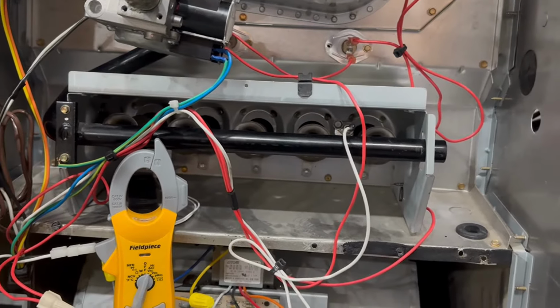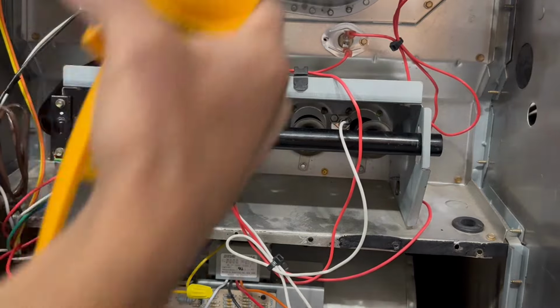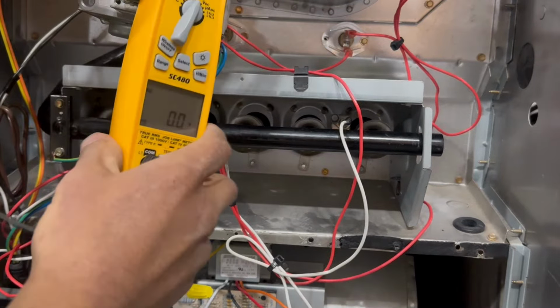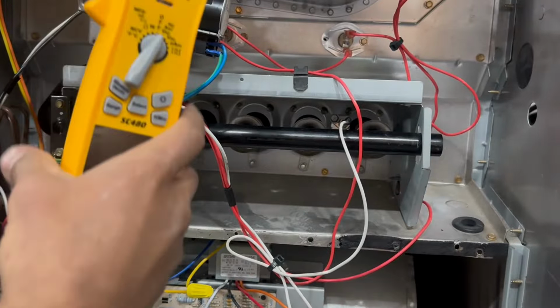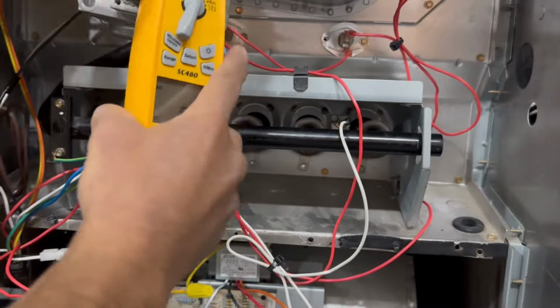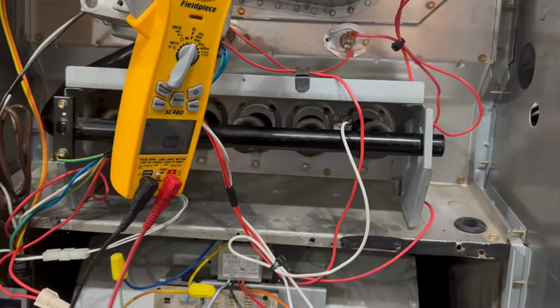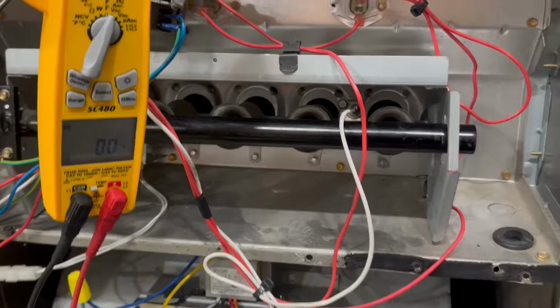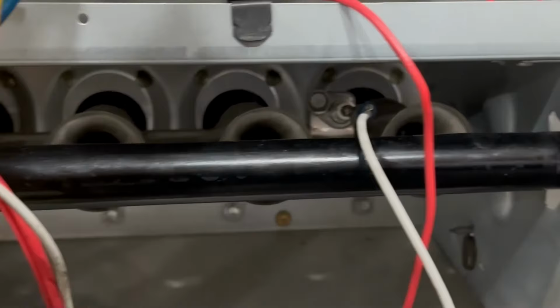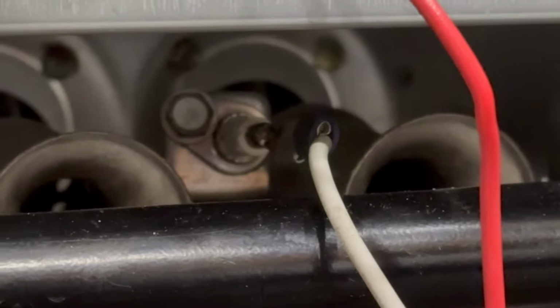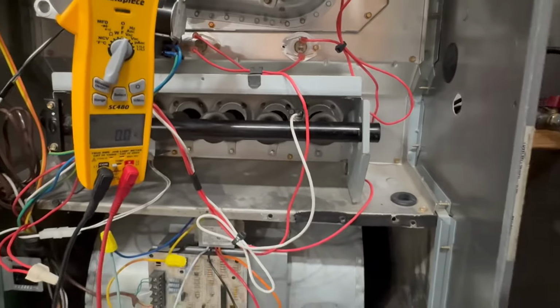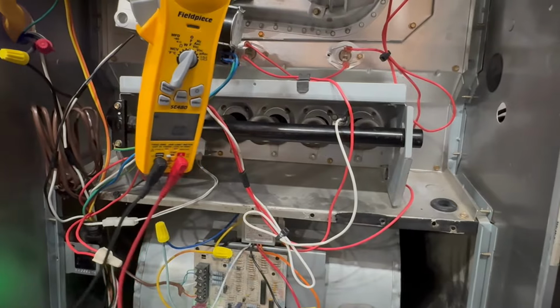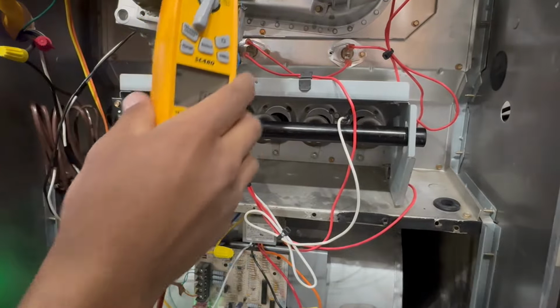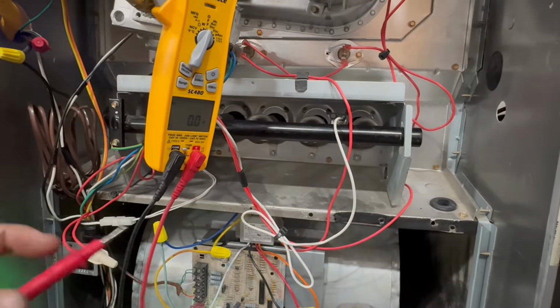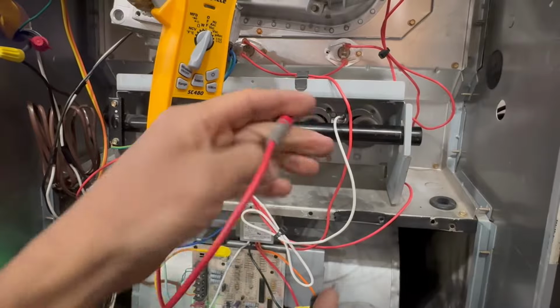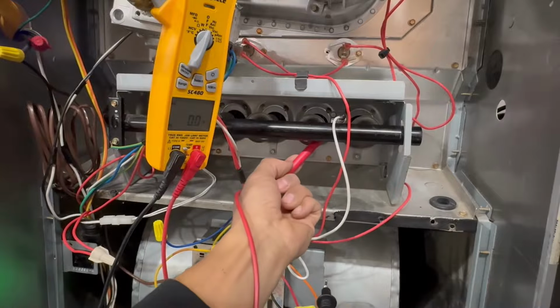The first thing is to make sure you have voltage coming in. Let me see if I can put this here so you guys can see the voltage. All right, there we go. You should be able to see that. You want to grab the metal part, right? You see right there, I'm going to put my lead there and the other to ground. You can put it to neutral too. Once I call for heating, put it on voltage. You want to make sure it's getting between 80 and 100 volts.